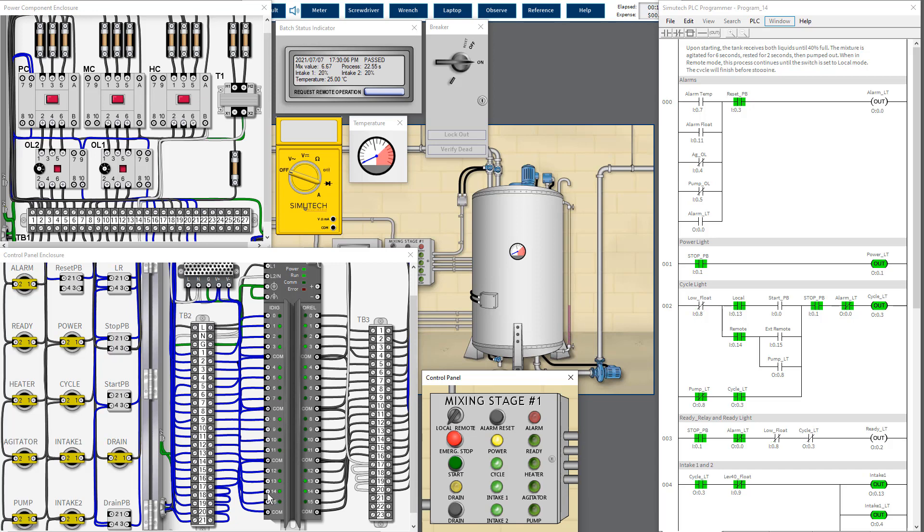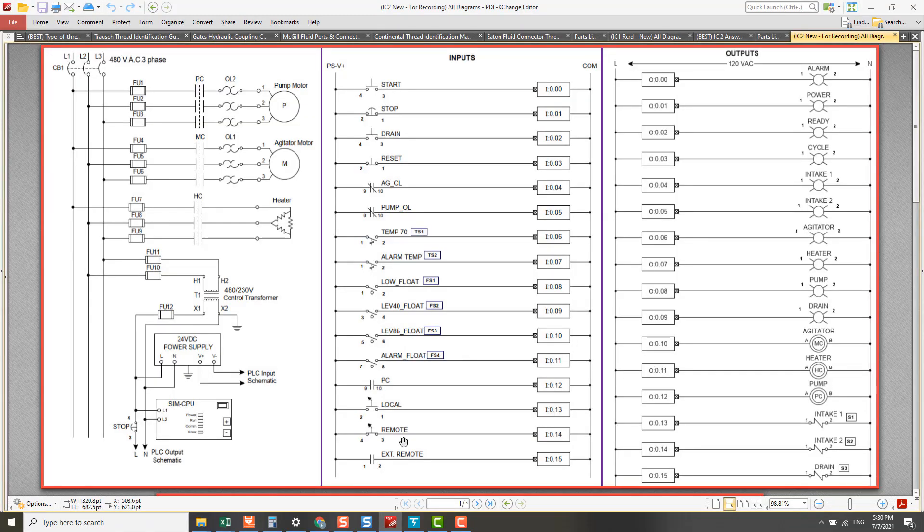The channel 14 LED should turn off. Why? You see here, this is channel 14 for PLC input channel load. It connected to the external input switch.